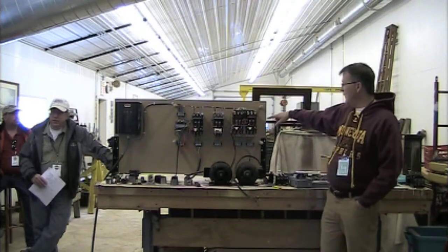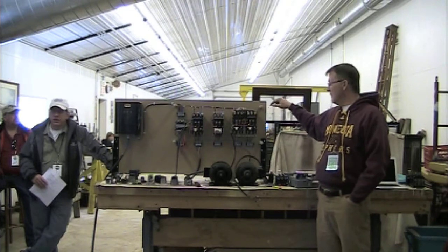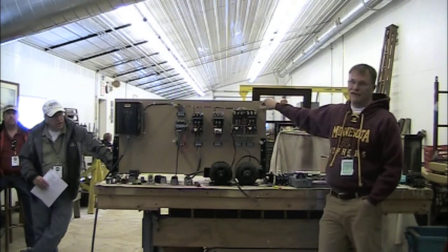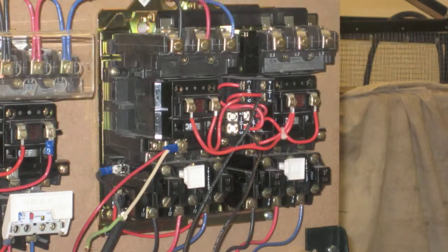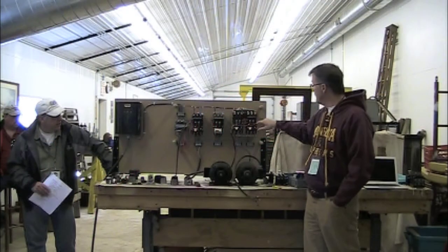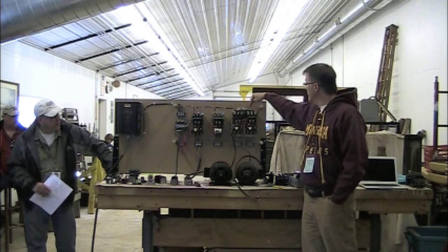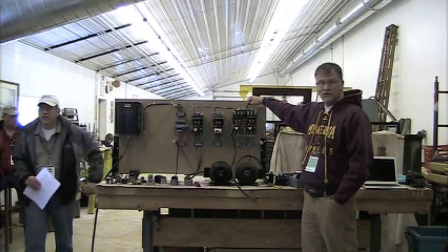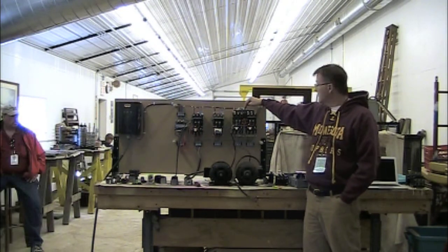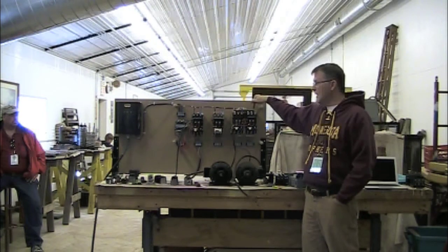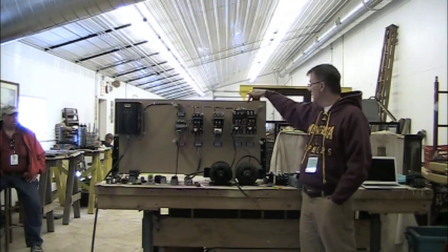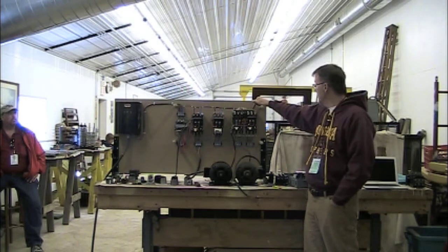The one next to it here, I brought as an example, is a Bulletin 520 2-speed separate winding starter. If you look at it, it looks a lot like the other ones, and in typical Allen Bradley fashion, it's made completely out of the same components. So it's got two 509s, it's got a set of jumper bars here that connect the input phase of each starter together. So you've got power coming into the top here. It's also brought over to the second contactor.